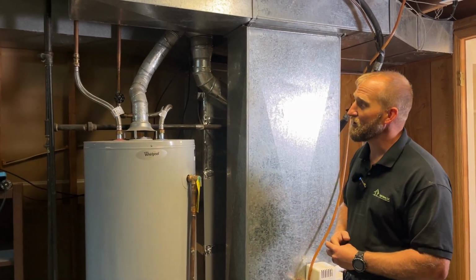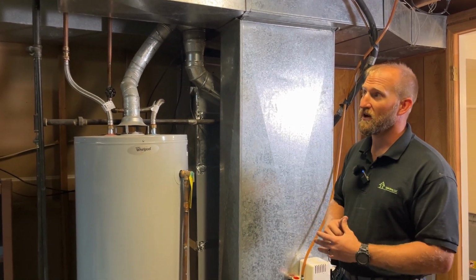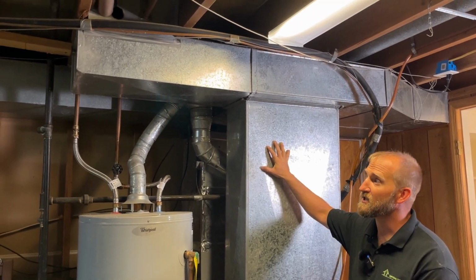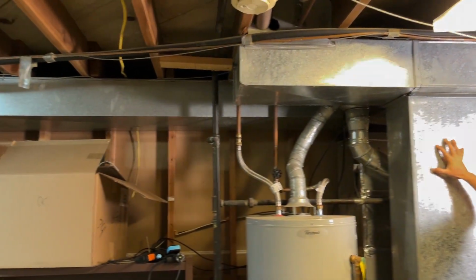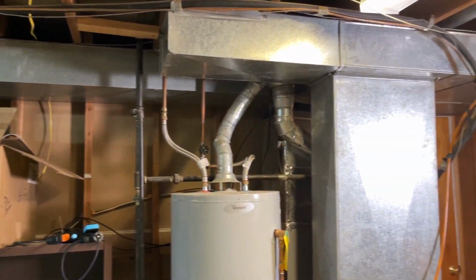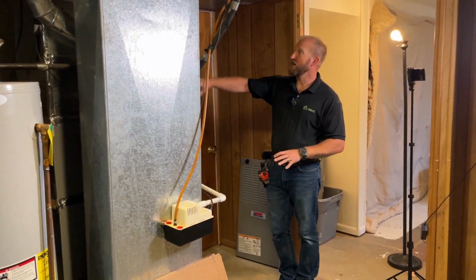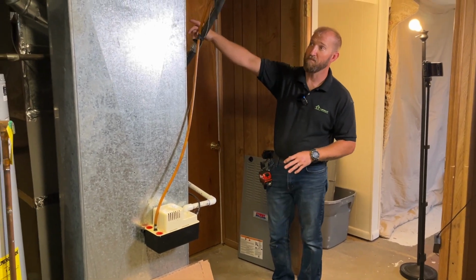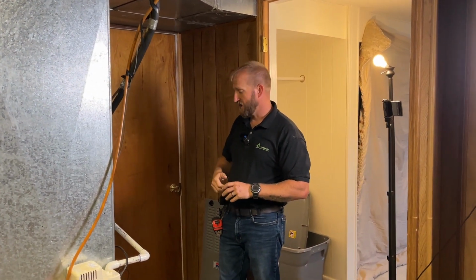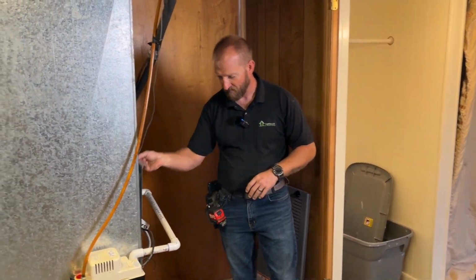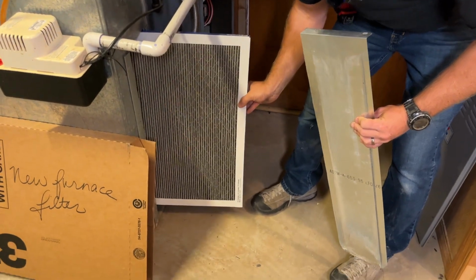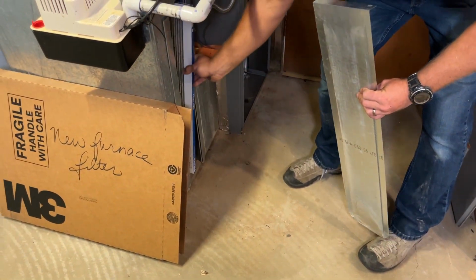So down here in our combustion air zone, the things that we're going to be looking at are our types of distribution system. So this is a ducted system, or a centrally ducted system. You've got your air drop or return air. You've got your supply coming up and your supply plenum going out to your branch ductwork. You're going to look for your filter. You're going to check to see the condition of your filter. This one's a little bit dirty, but it looks like it's all right.